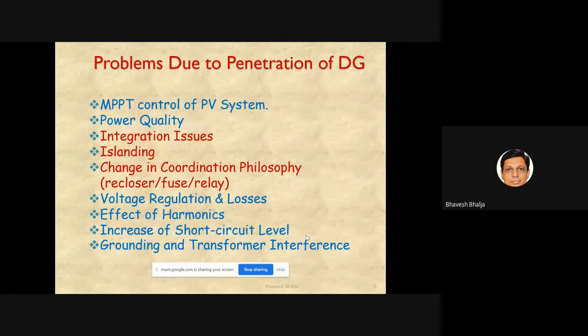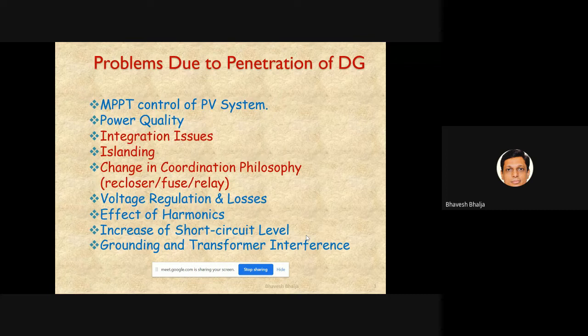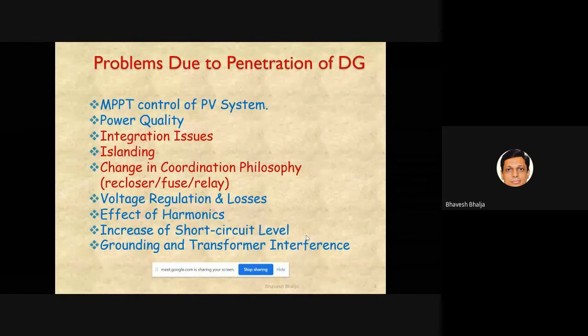So the function of a recloser is, whenever a fault occurs, we know that the circuit breaker opens, right? The three poles of the circuit breaker open. After some time, it will reclose automatically. That is the function of a recloser. So if a transient fault is there, it dies out, right? We know that 80% of faults are transient in nature. So it will die out automatically.